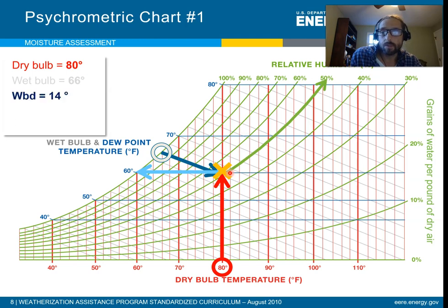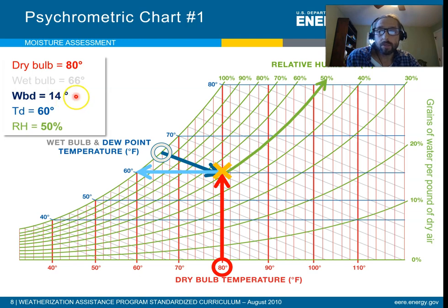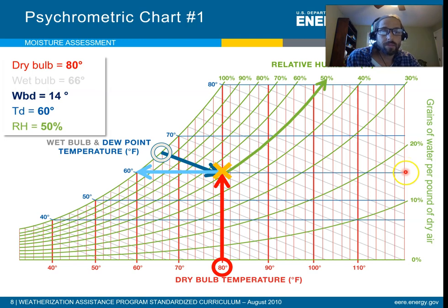Our wet bulb depression is 14 degrees, which is the difference between the dry and the wet bulb. Our dew point — you follow directly to the left — and that's 60 degrees. So you can tell your dew point as well, and the relative humidity is 50%. In the previous lesson we just looked at the wet bulb depression and found the relative humidity based on that. But as you can see, if you have these readings with a psychrometric chart, you can tell a lot of other things, including the absolute humidity if we had units over here.